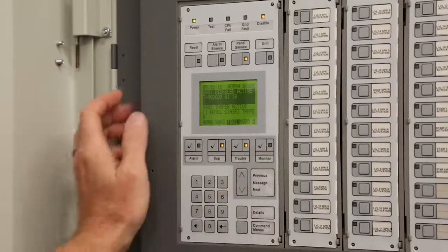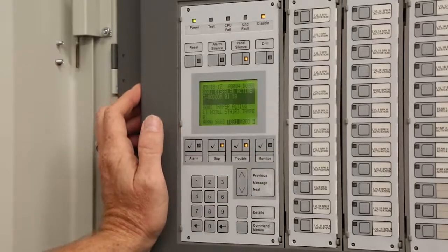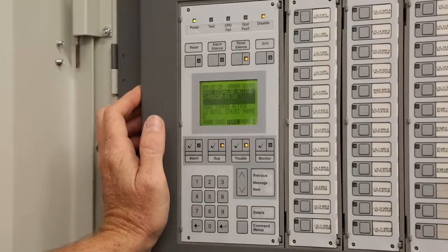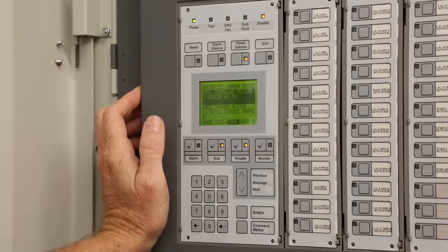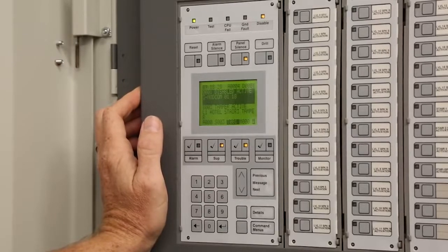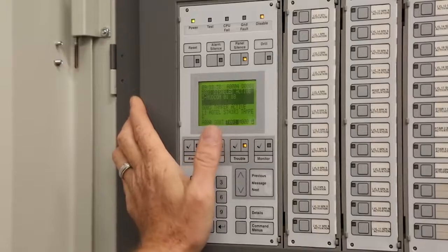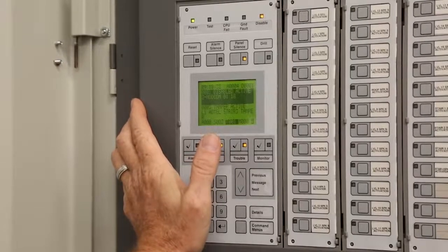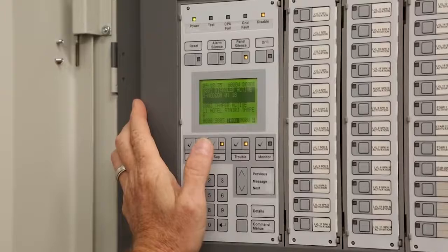Monitor points are basically any damper, the damper indication, or fans are monitored. If we are in smoke control mode and we do have a smoke detector go off on a floor, this can actually go up to 60 points because there'll be monitor points on your dampers and fans and all that. Also, monitor points would be any switches that are activated here.